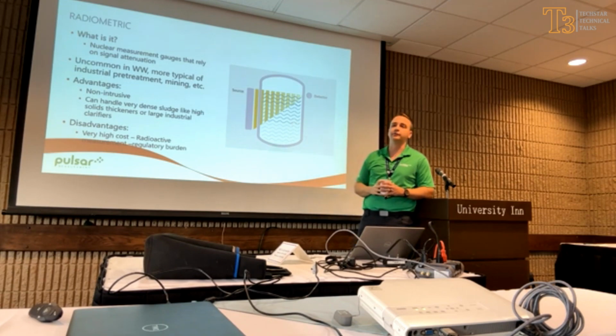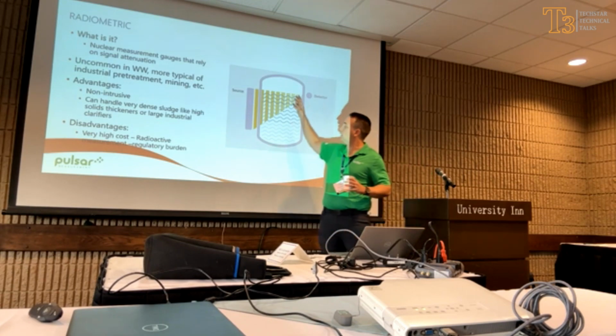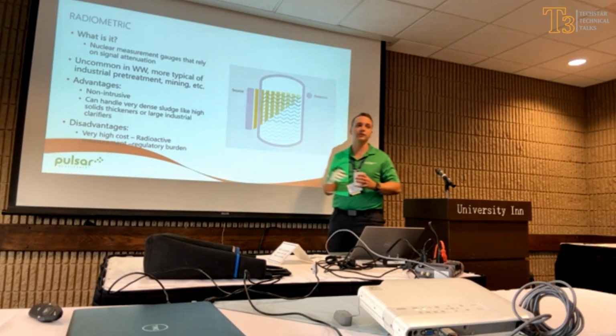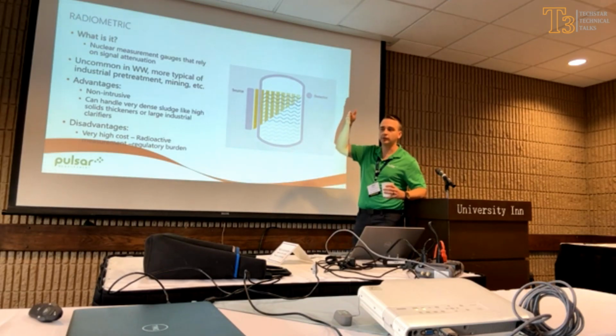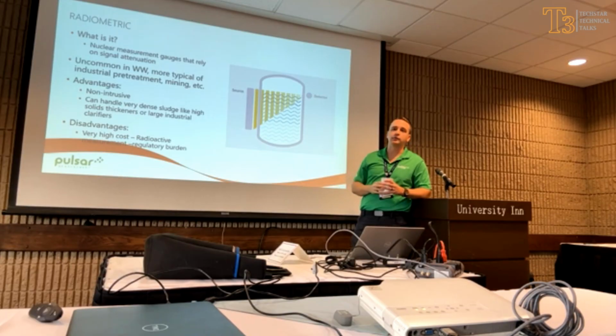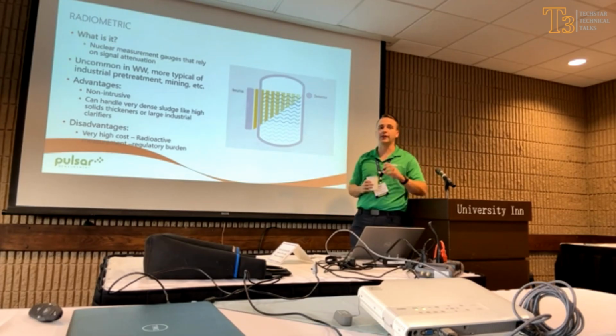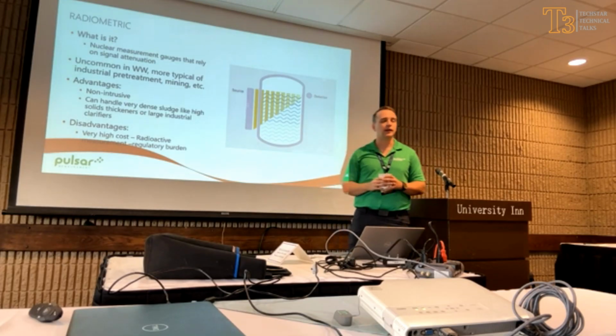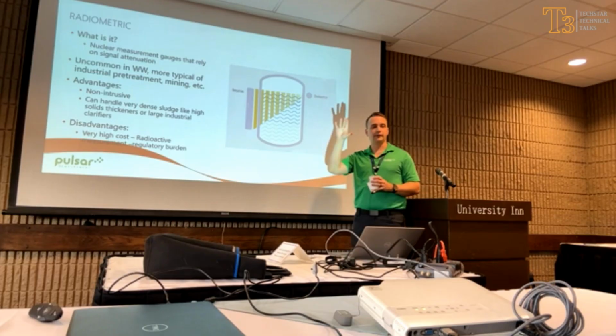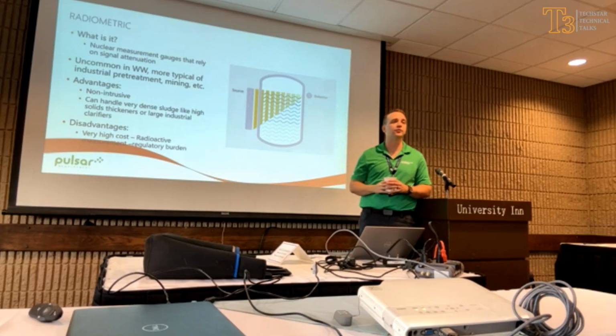Based off the deflection, there's an emitter and something on the other side of the tank that can read it, looking almost like a rack of temperature probes on the side of the tank. It reads the density of the sludge based on how that signal is attenuated, meaning it starts off with a really big signal, and it gets smaller the more sludge it has to fire through.